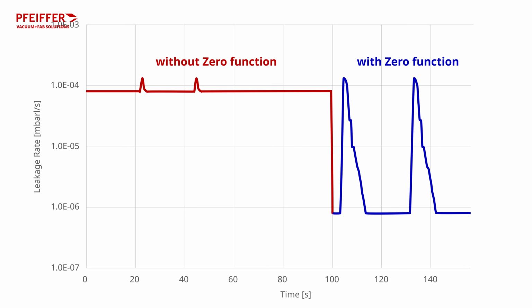A high background means that the signal that you want to measure is small compared to the signal that the leak detector displays during normal measurement already. What can be the root cause of this high background?